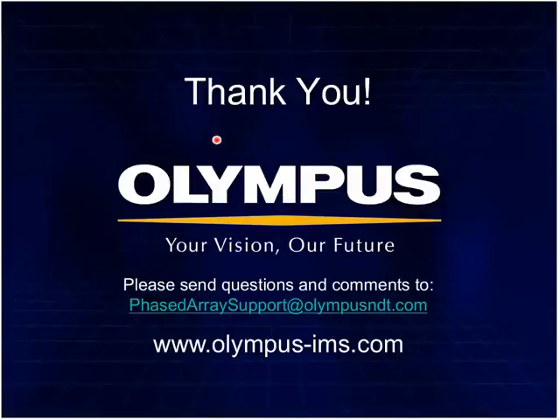So I saw we had quite a few questions during the presentation. The MX2 can display up to 4 groups of TOFD and 4 groups of phased array simultaneously using software version V4 or later. That's a very important point. And on the full versions of these training PowerPoints that you'll see in the download, there's some more images and some more examples of that. Good question. There were several other questions that we didn't have time to get to. We will answer all of those for you in the email blast that follows this up.